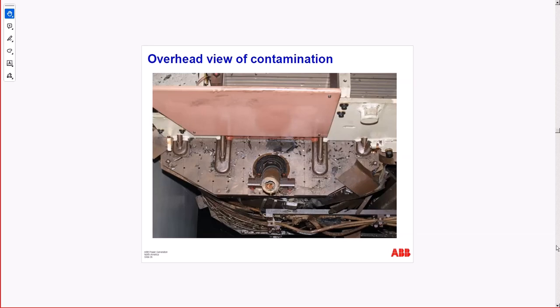Contamination: anything that is FME cannot go in the tank. We had that also, people drilling in the tank to hook up different wires for fire protection alarms, and they didn't realize that the edge of the tank is actually part of the tank, and the oil spilled out. It happened in Darlington back in 2019. We had some silicon filled 20 megawatt transformer, and they tried to reposition the fire protection alarming wires, and they considered it okay to drill in the edge of the tank, but it was not.